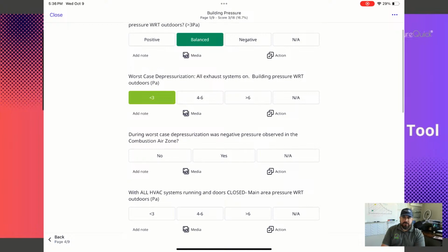Worst case depressurization: I'm turning all the exhaust systems on to see what the house depressurizes to. If it has a fireplace, we could have an early morning situation where all the bath fans are on, people are showering, making breakfast, running laundry, and the house depressurizes to the point where fuel-burning appliances within that envelope can start backdrafting. So I'm going to see what that worst case depressurization is.